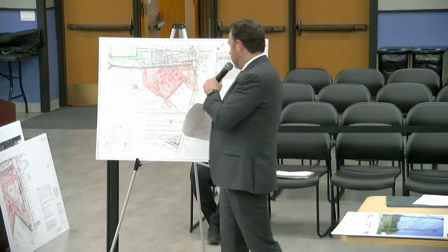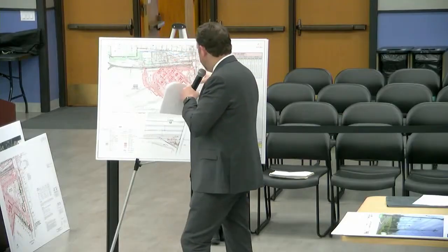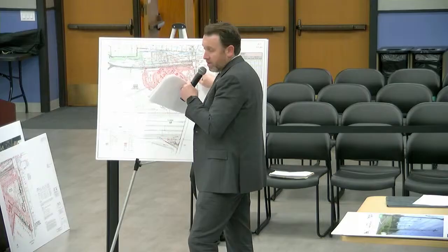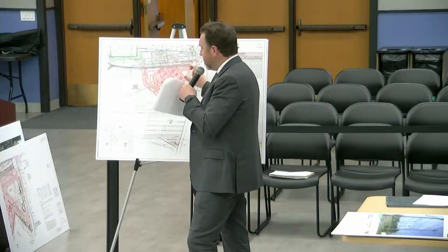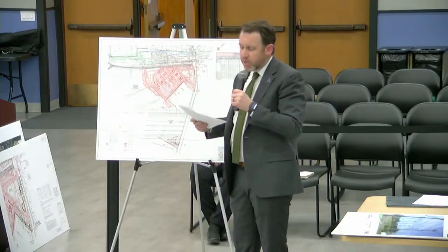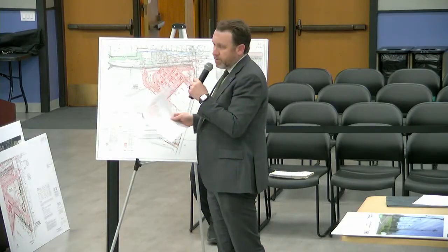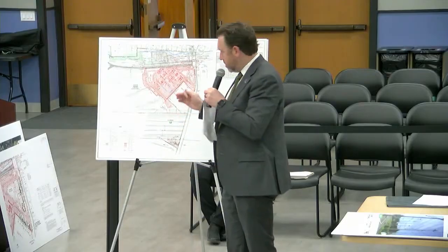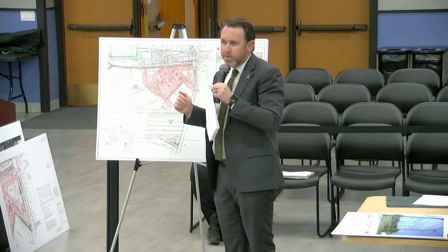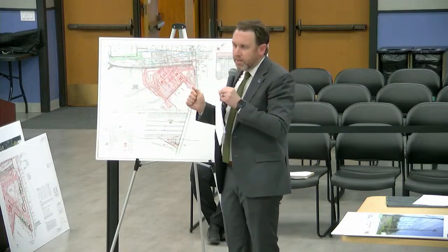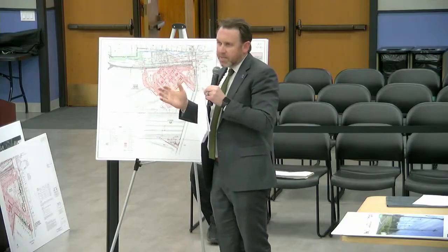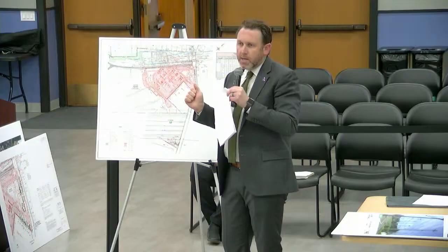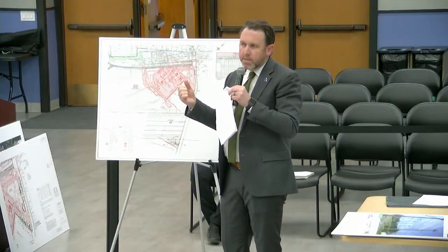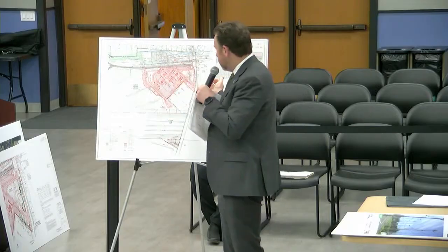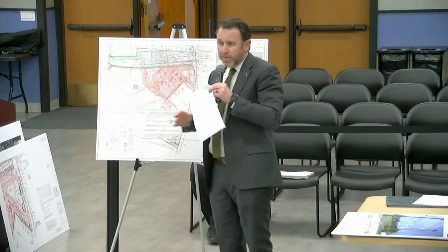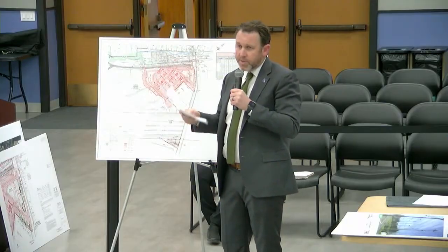Back to the station proper: we've proposed two access roads, both off Meadow Road, 16 feet wide. We're requesting a variance since the minimum standard is 22 feet for two-way traffic, but since this is a private access road without regular two-way traffic, 16 feet is sufficient. This is PSE&G's minimum requirement and allows enough room for construction access, heavy haul equipment, and fire apparatus to enter the station if needed.